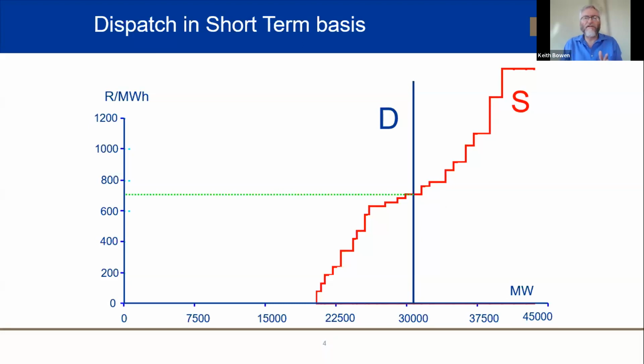Often that's about 60% of the maximum rating, sometimes more, sometimes less. But that is where you would schedule to start from. So if you're planning for tomorrow and you've got a peak and you're optimizing over the whole 24 hours, you will find that there will be some good 6 to 8 hours between 10 o'clock at night and 6 o'clock in the morning where you might be running generators at their minimum, because taking them off is not really a feasible option, and they can't run above that point because it's just too expensive. So they would run through the night at their minimum.